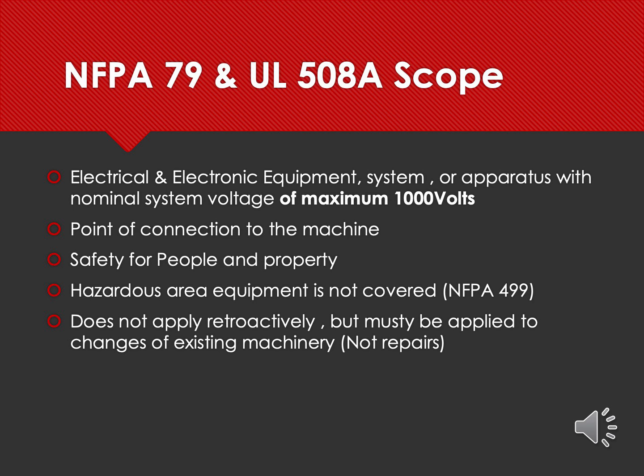The next bullet is that hazardous area equipment is not covered in these standards. Hazardous areas are covered in the NFPA 499 standard. The last bullet is that it does not apply retroactively, meaning you don't have to comply with every new version of the standard as it gets released after the equipment is installed and put in service. However, it must be applied when you make specific changes to existing machinery. You can just exempt repairs from that equation.